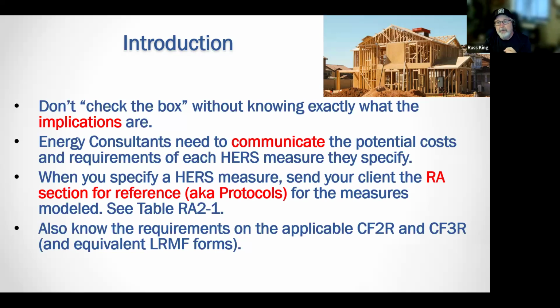Step 3 is to have that house tested and inspected, either by the local building department inspections or the HERS rater, to make sure those things are done correctly. In the commercial world, that's called commissioning — you build a complicated building and have people come make sure it works as designed. Same thing for residential: figure out what you're supposed to do, install it, have somebody test it.